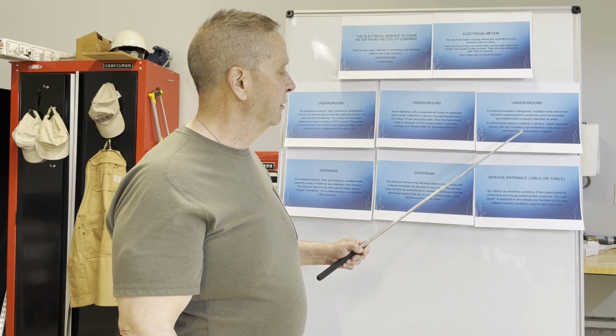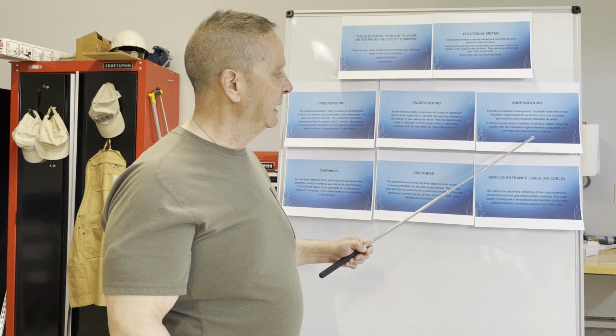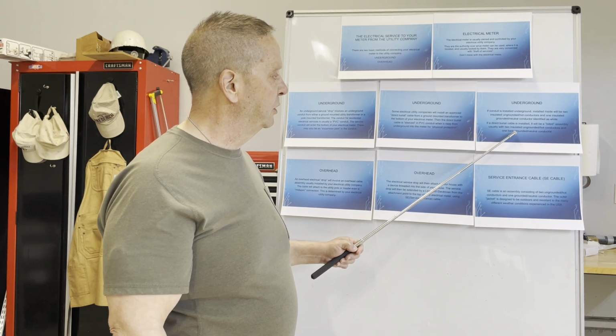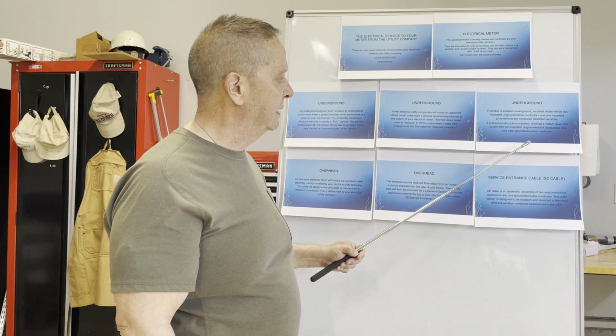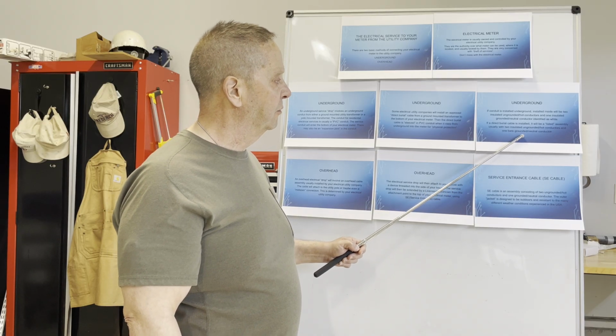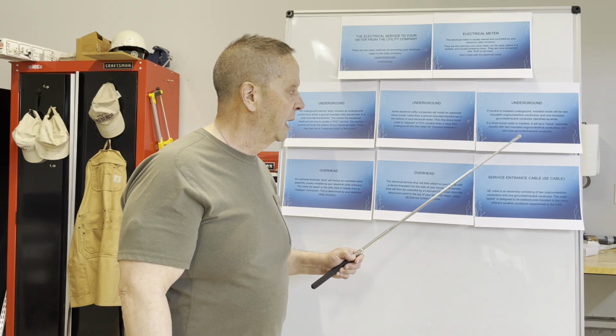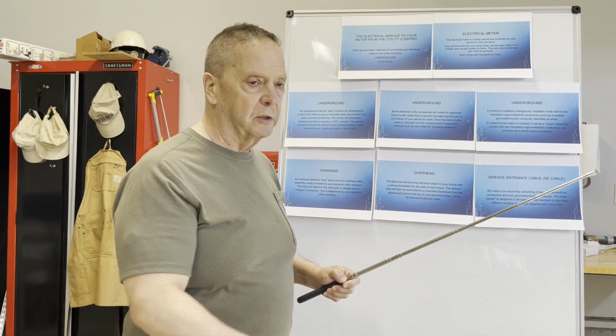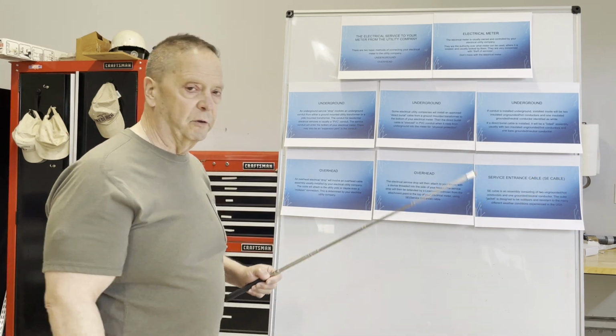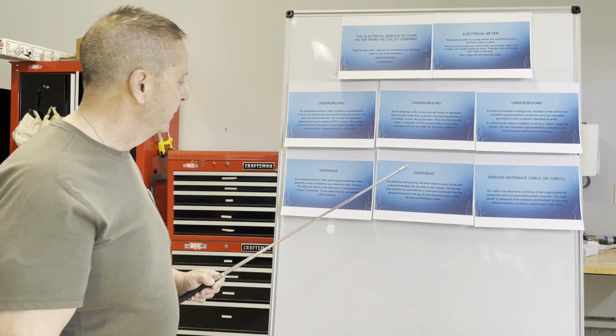If direct burial cable is installed, it will be a listed assembly, usually with two insulated, ungrounded hot conductors and one bare, grounded, neutral conductor. I'm not sure why they run a bare conductor underground. That's how the manufacturers manufacture it though.